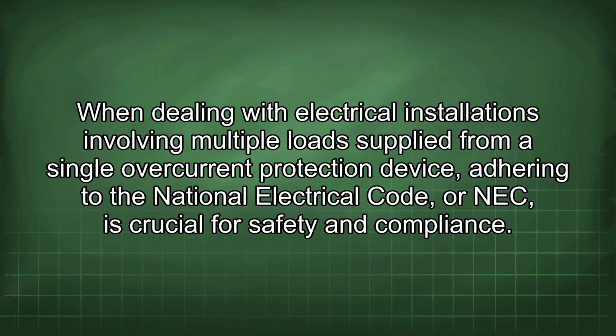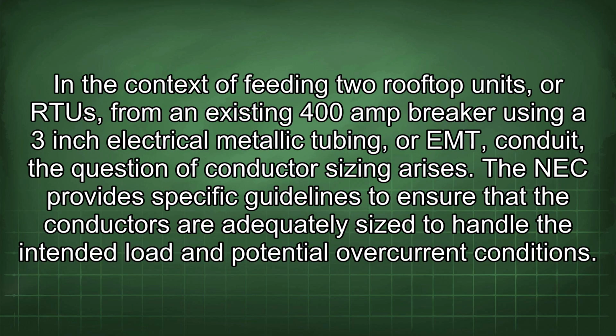When dealing with electrical installations involving multiple loads supplied from a single overcurrent protection device, adhering to the National Electrical Code, or NEC, is crucial for safety and compliance. In the context of feeding two rooftop units, or RTUs, from an existing 400 amp breaker using a 3-inch electrical metallic tubing, or EMT, conduit, the question of conductor sizing arises. The NEC provides specific guidelines to ensure that the conductors are adequately sized to handle the intended load and potential overcurrent conditions.